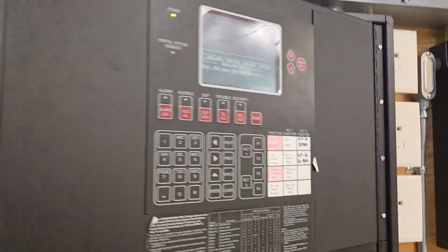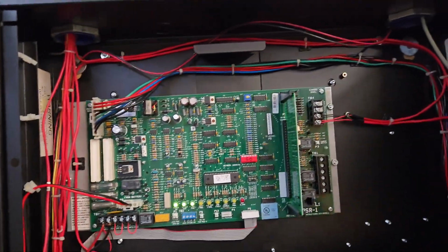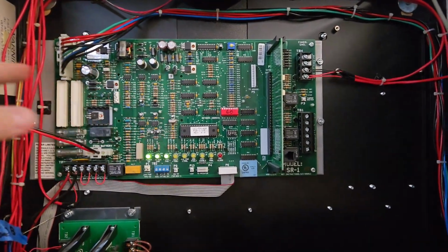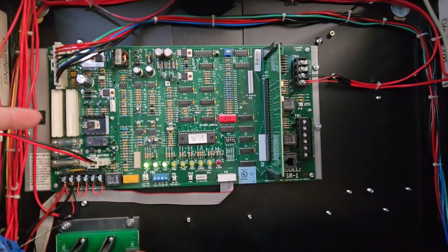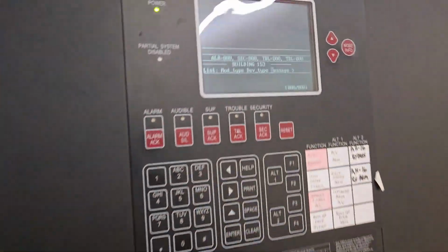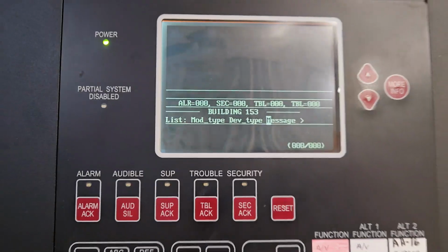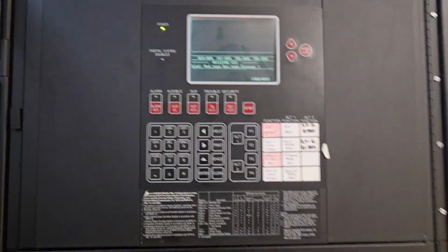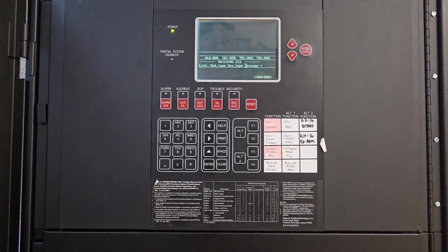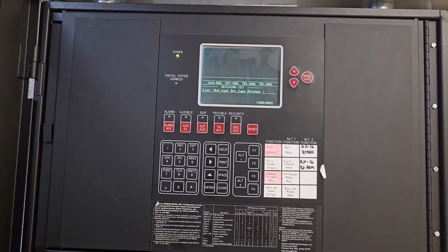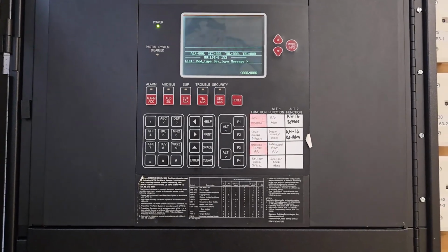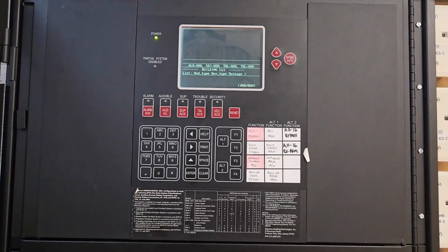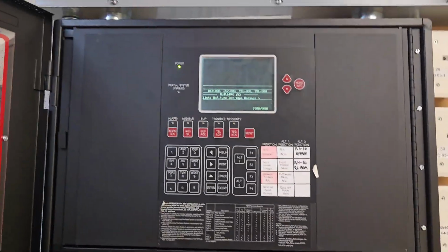So traditionally, you'd open this up, and this is a node card, but you would have your wires you'd be pulling off of the card, which would give you a list of troubles, and then they would appear on the panel, and you can go through the list that way. So this is just an easier way of doing it for the digital interface. But in advance, though, you're going to need to know like how many loops, devices on the loops, things like that. So I already know on this particular system, it starts at loop 1. So I was like 001, then 001, loop 1, device 1, and I just went from there.